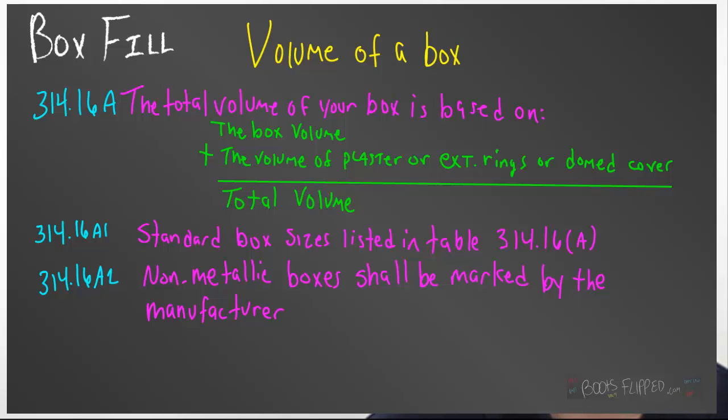That's 314.16a. In 314.16a1, it talks about standard size boxes that are listed, and you'll see those in table 314.16a. In 314.16a2, it states that non-metallic boxes shall have the volume marked by the manufacturer inside the box. Take a look next time, and you'll see that. Inside the box will be marked cubic inches. If you look inside of a two-gang box, a lot of times you'll see 36 cubic inches, and that's how large the box is, and that's what you use for your box fill calculation.